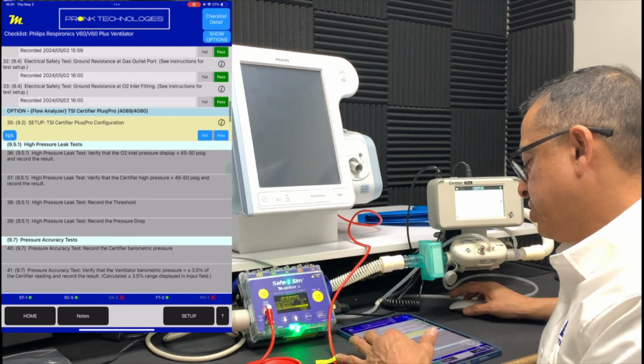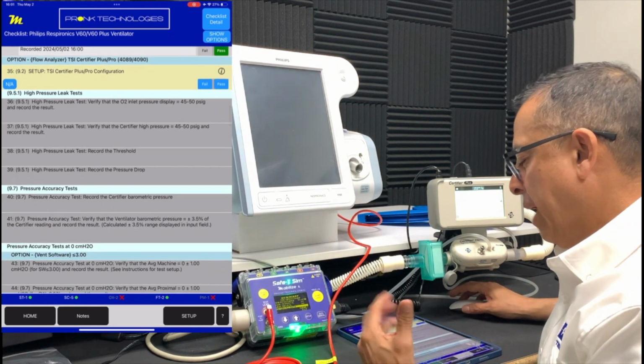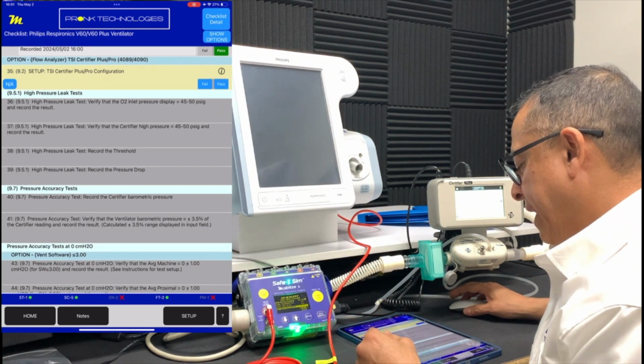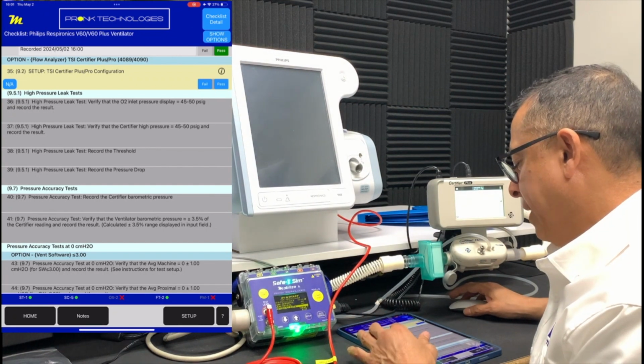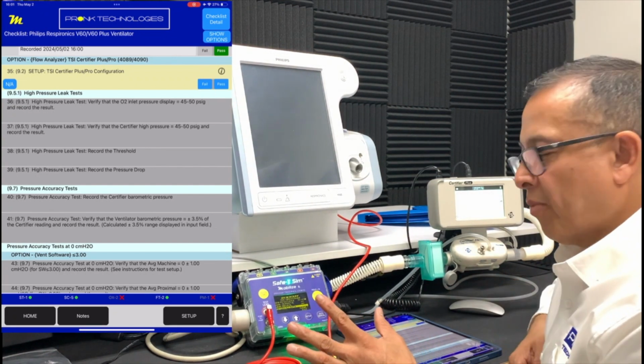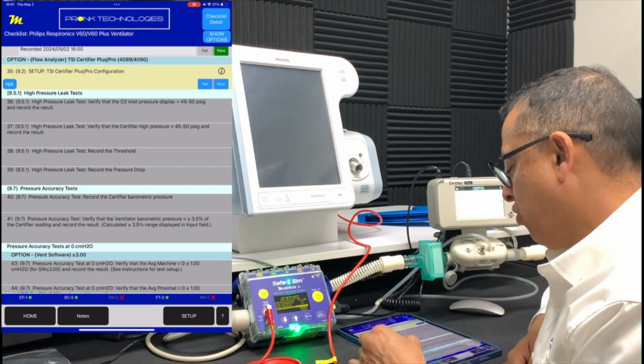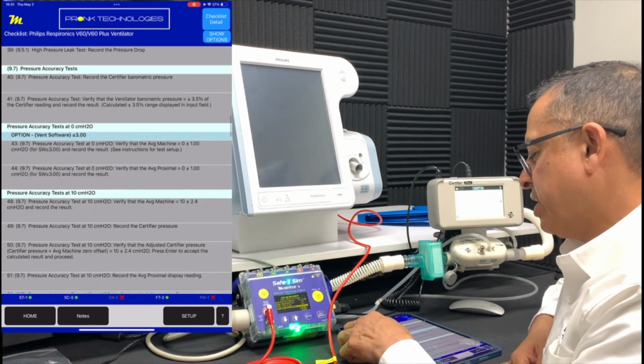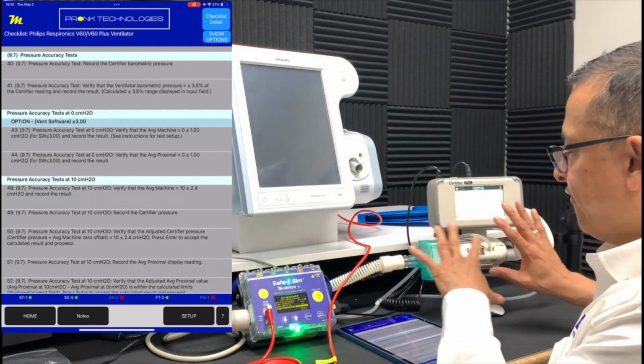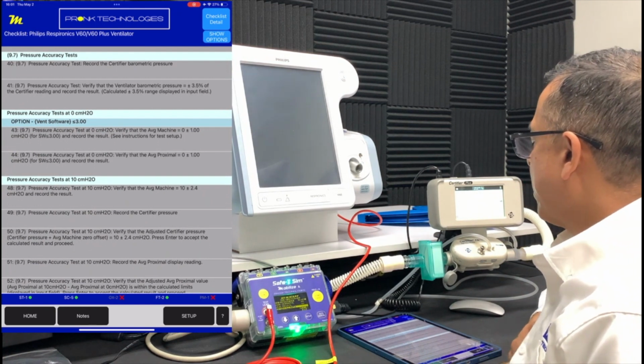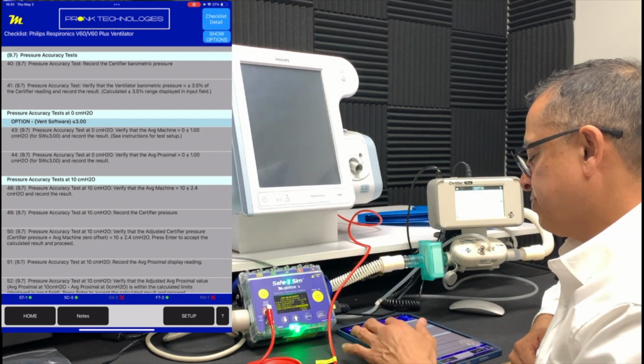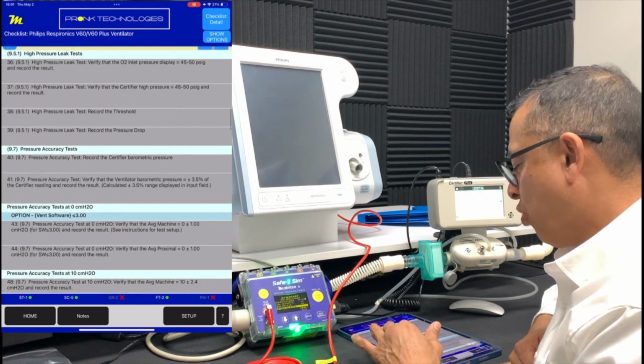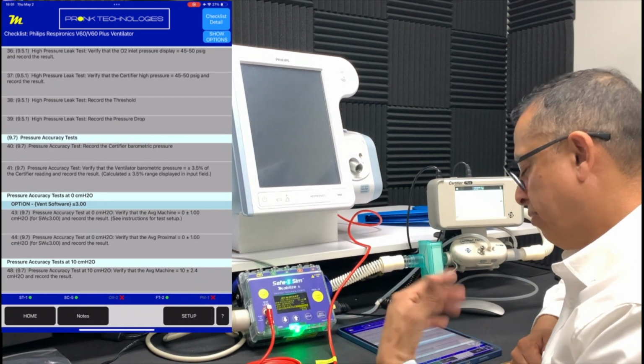The next one is to start doing our high pressure leak tests. And we want to make sure we do those tests, of course. For the purpose of this video, we're going to go straight over to the pressure test and go through that, because that involves running the Certifier Plus to perform those tests. But of course, the high pressure test is important to do. Not suggesting it's not important, but it's pretty straightforward.